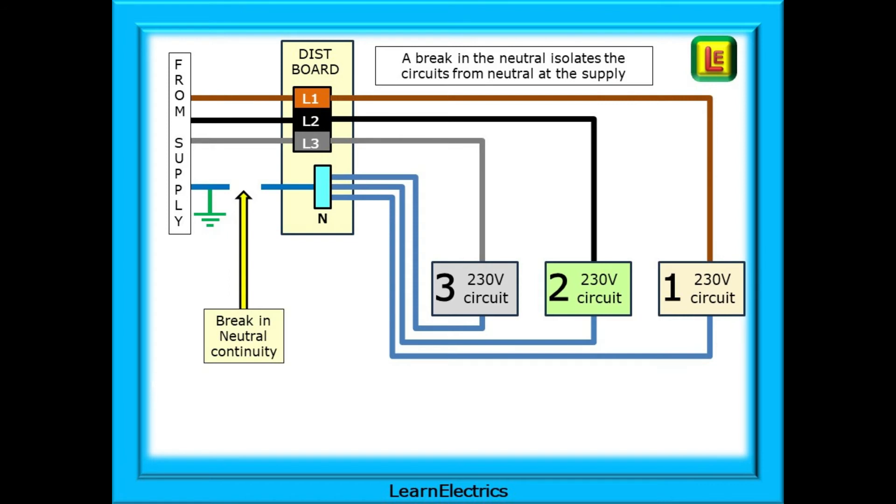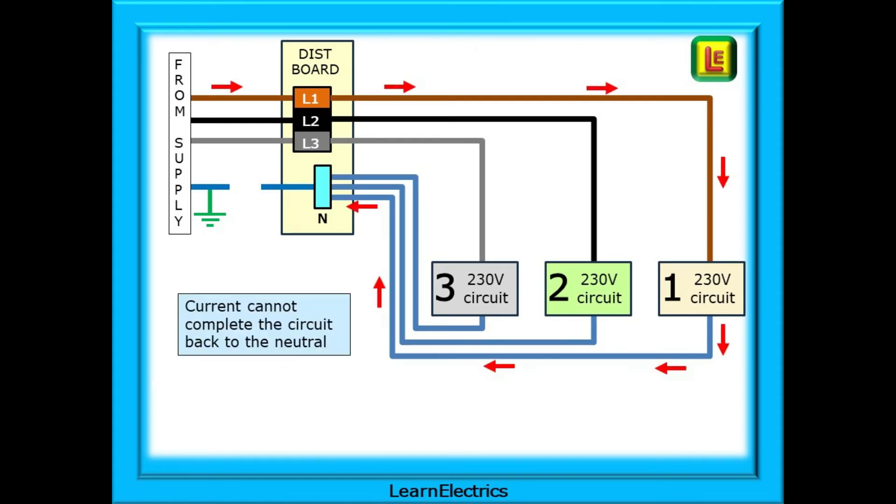On this slide, we can see that the neutral from the supply has been damaged. There is now no neutral connection at the distribution board. But the neutrals for all the single phase circuits are still intact, still in place. Each single phase circuit is still connected to the neutral bar, and each circuit is still connected to its own circuit breaker. The current flowing through L1 would like to flow through the attached number one circuits, but their exit from the installation is prevented by the broken neutral on the upstream side of the distribution board.